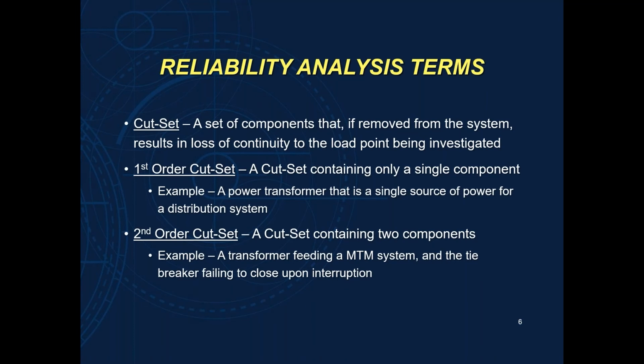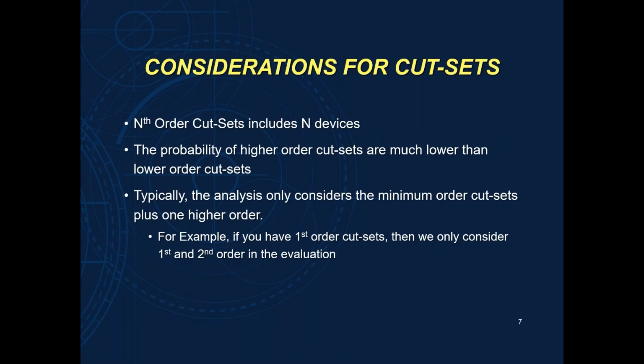Obviously, this can go as far as you want it to go. We can have third order, fourth order, et cetera, depending on however many combinations of component failures will take you out of service. Well, we don't want to go that far into it because it can go to infinite orders. So what we're going to do in the case of the IEEE Gold Book method is we're going to determine what the lowest order cut set is, and then we're only going to consider the next cut set above them. Anything beyond that is really going to be negligible by comparison when it comes to calculating your availability values. So for instance, if you have first order cut sets, you have one component that will take out your entire system, then we're only going to look and evaluate at first order and second order cut sets, okay?